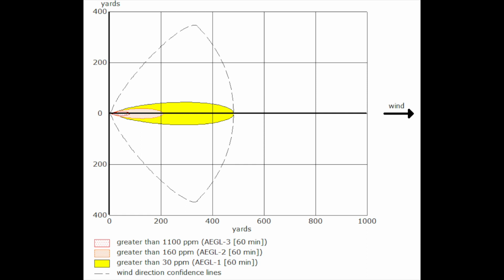This really is good data to tell you whether your PSV is discharging to a safe location and whether you are impacting anybody if you were to have a release. What we don't want is to prevent the equipment from rupturing, but then impact somebody by where we have this discharge going. So those are key things to think about whenever you're looking at the discharge assessment of your relief device.